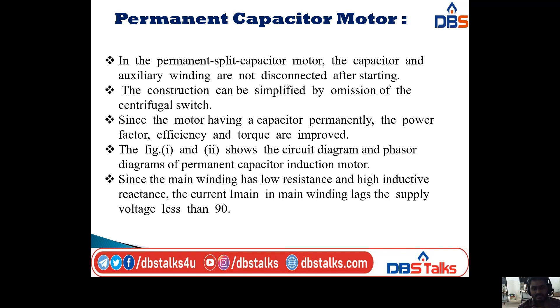In those three methods, we used some capacitor in series with auxiliary winding. In all the circuit diagrams, we have two windings: one is main winding and the other one is auxiliary winding. In those methods, we removed the auxiliary winding after starting the motor. But in the permanent capacitor motor, the capacitor and auxiliary winding are not disconnected after starting. The construction can be simplified by omission of the centrifugal switch.